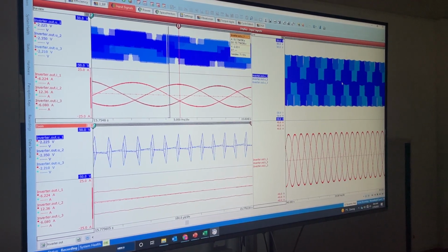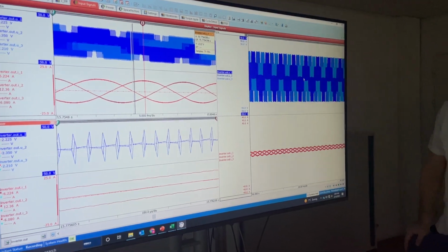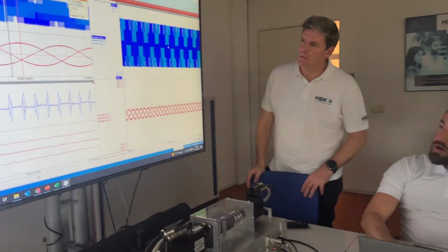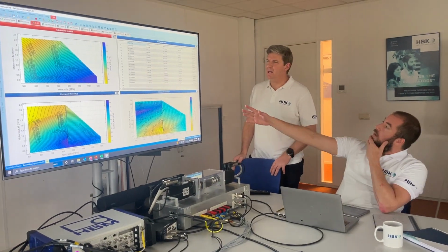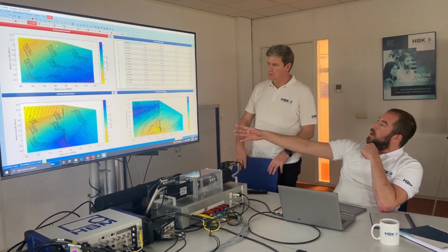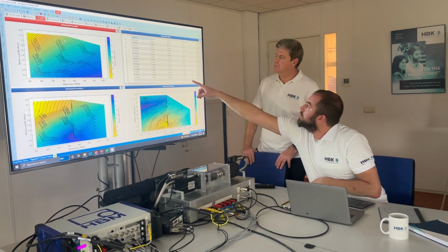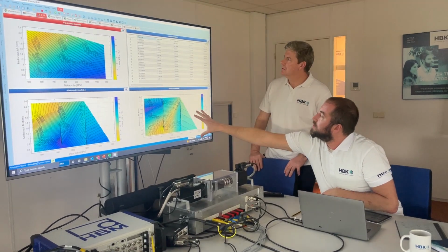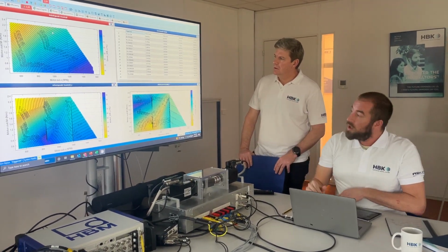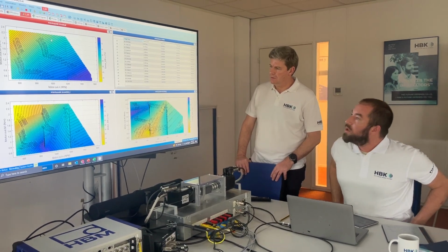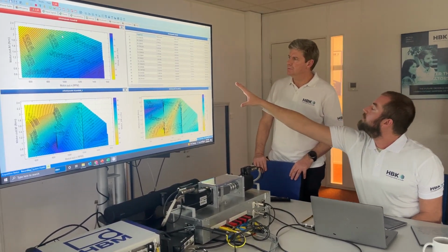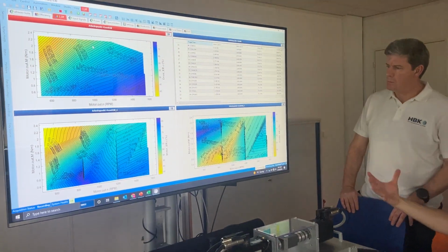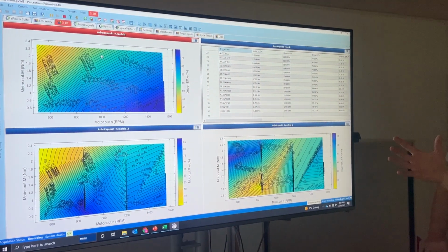So here in the more production optimization test, you kind of know what you're looking for. So you only need data at those specific points. Got it. Okay. But what we're really after is these efficiency maps. Yeah. And we've got our torque, we've got our speed, we've got our drive efficiency, and then we've got our efficiency maps, which is pretty cool because we've got this Excel type data where the people who just want to look at the top line numbers have their Excel data.